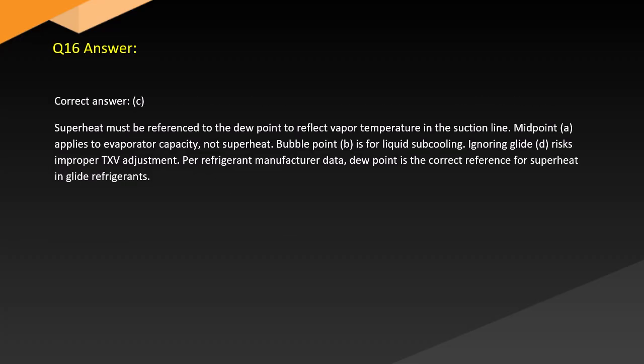Answer. Correct answer: C. Superheat must be referenced to the dew point to reflect vapor temperature in the suction line. Midpoint, A, applies to evaporator capacity, not superheat. Bubble point, B, is for liquid subcooling. Ignoring glide, D, risks improper TXV adjustment. Per refrigerant manufacturer data, dew point is the correct reference for superheat on glide refrigerants.